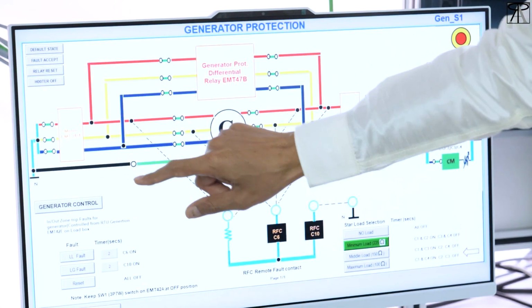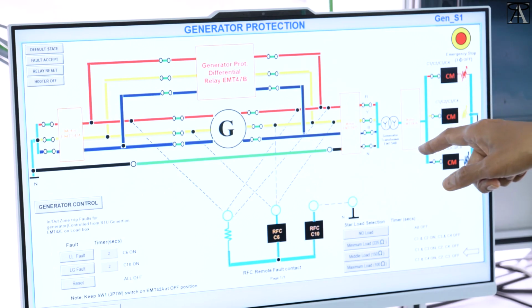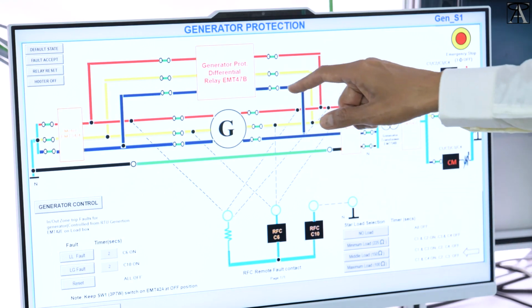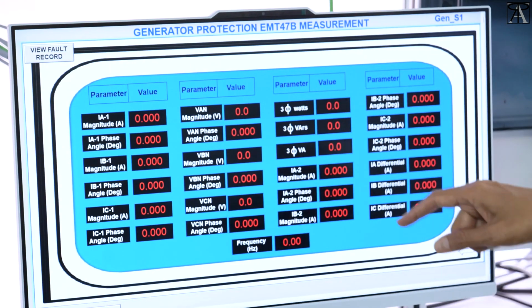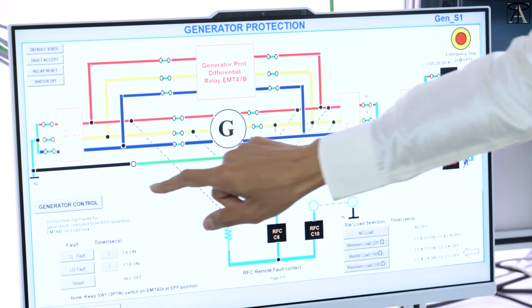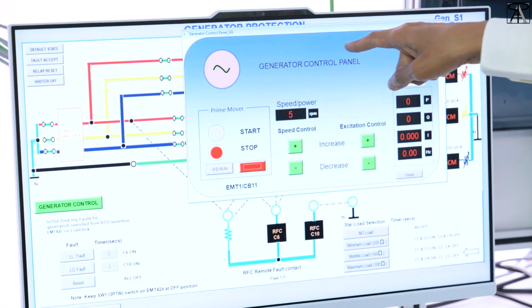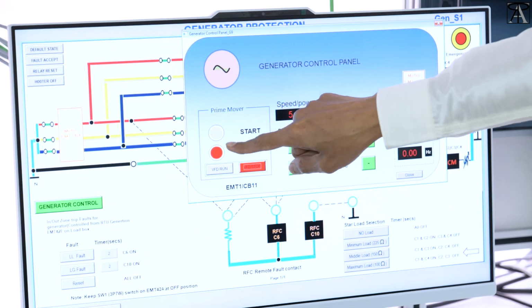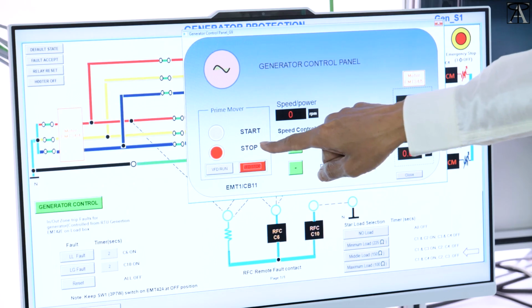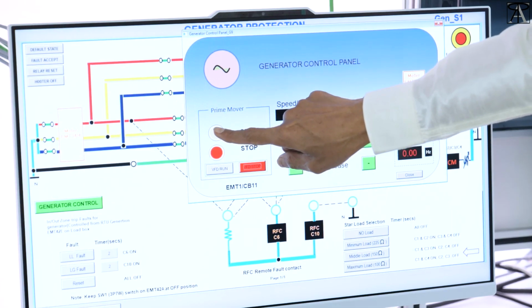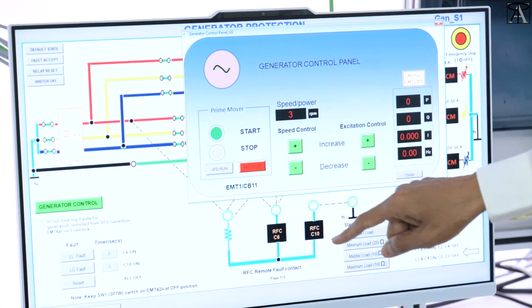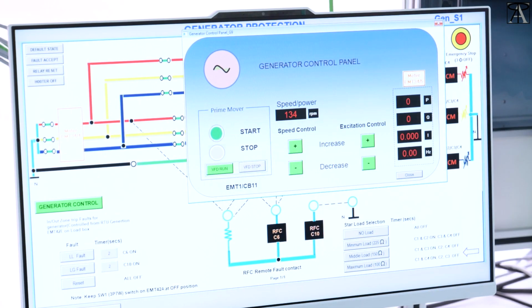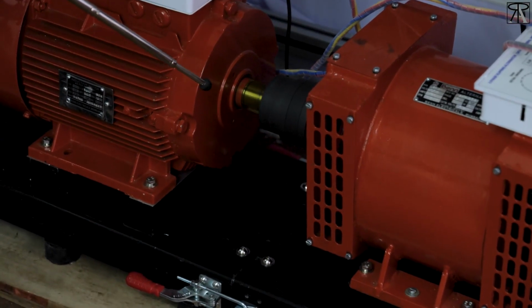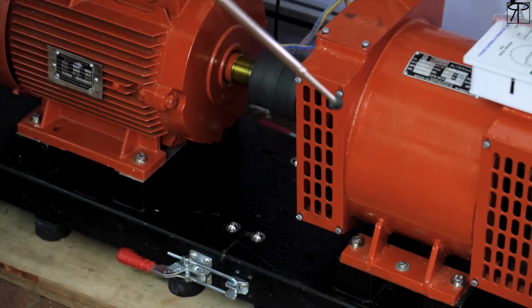Now we start generator protection. This is the generator protection relay. Now we start with the generator. This is generator control. We can start the generator with the start button and stop it with the stop button. So we touch the start button, and the green LED will come on. VFD run. Now the motor is rotating in clockwise direction and generator voltages are coming here.